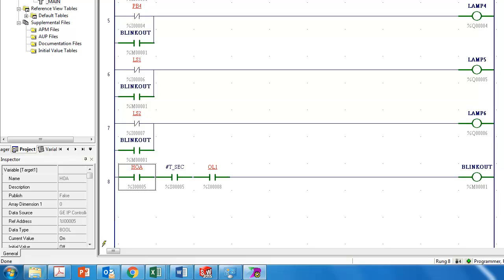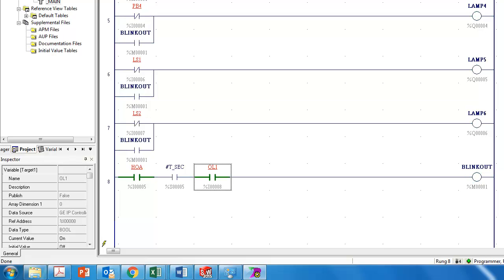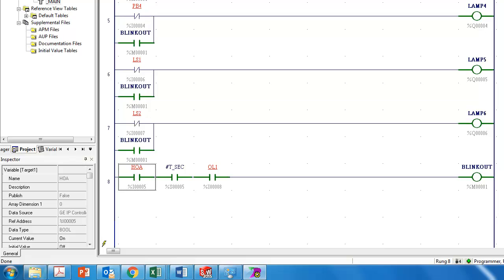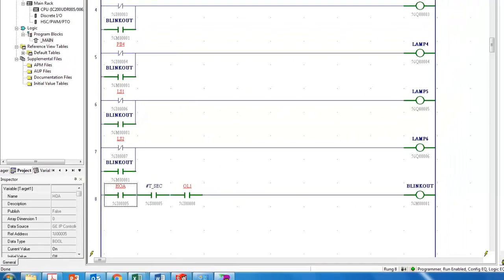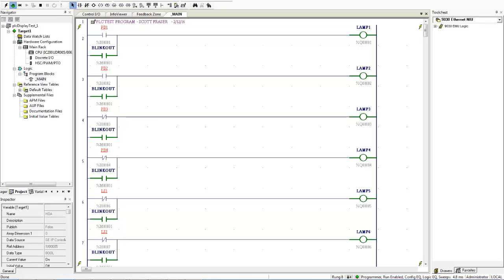Now to test it OL input toggle it switch it okay blinking should stop. Turn it back on again and toggle your HOA. In order for Blink Out to work you should have green green green every time you have a break and no green that means you have a break in power flow and the coil will not be energized. So hopefully everything you have now is working and it's a quick way to test it. And I just hit F12 and shut everything off.